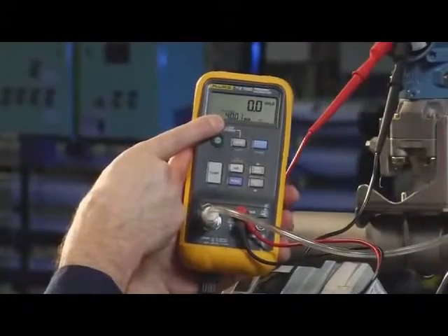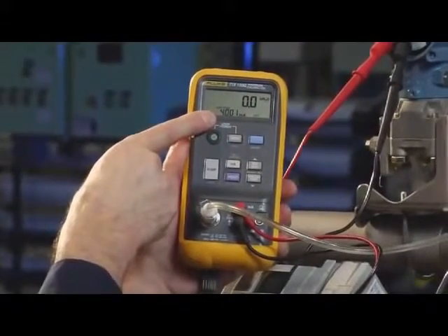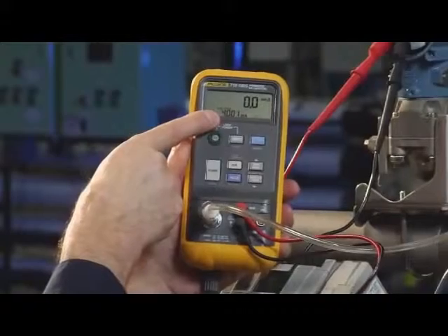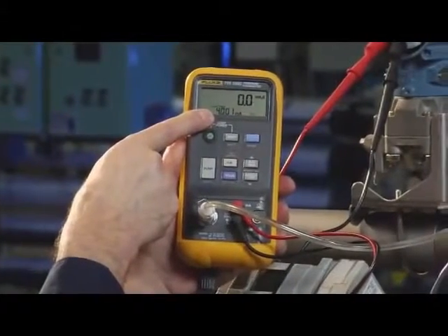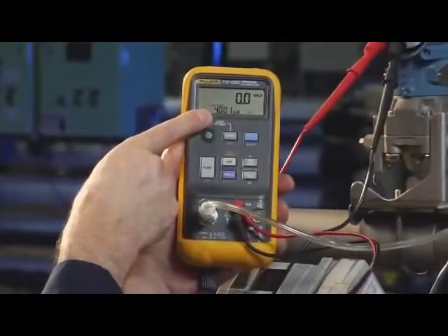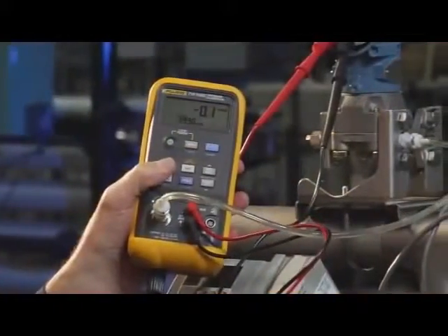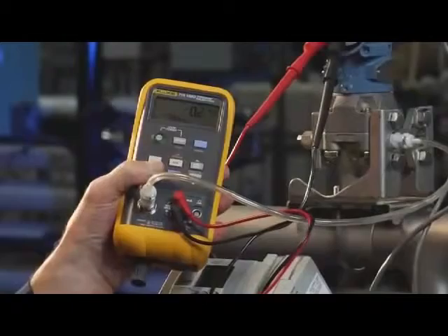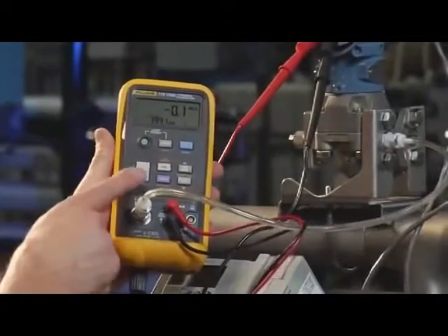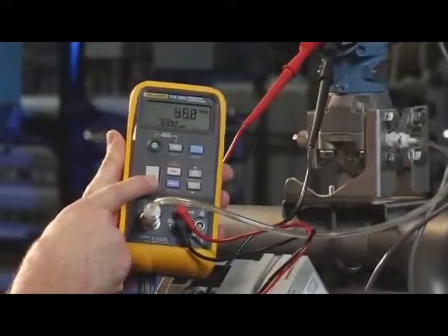First, we apply 0 inches of water. Measure 4 milliamps. Any deviation from 4 milliamps is calibration error. Next, close the vent valve. The next test point, 50%, is 100 inches of water. We'll use the electric pump to generate 100 inches of pressure.